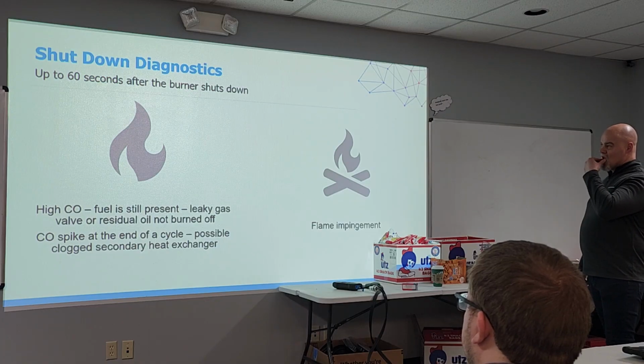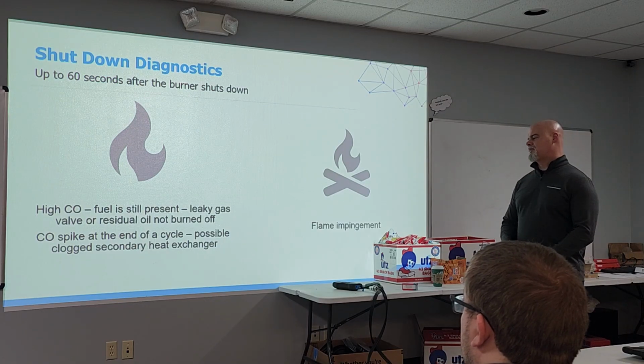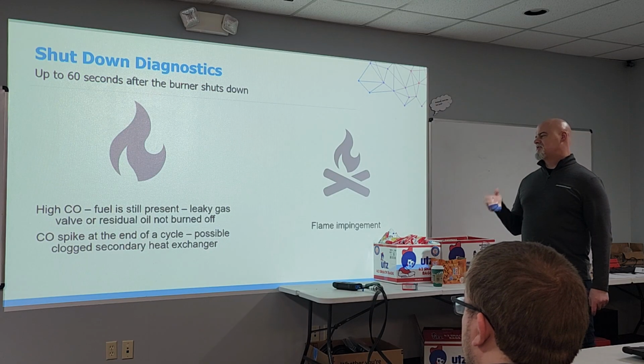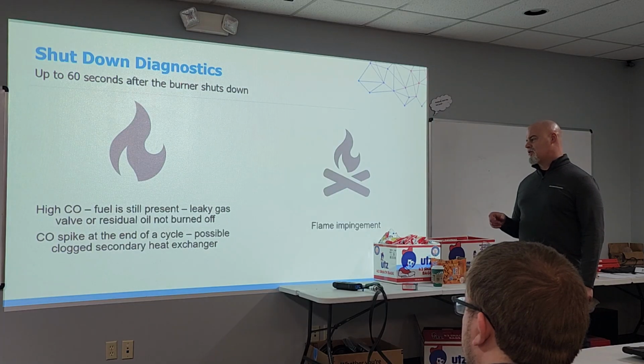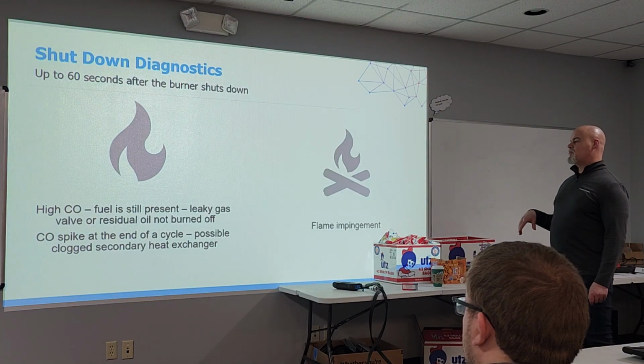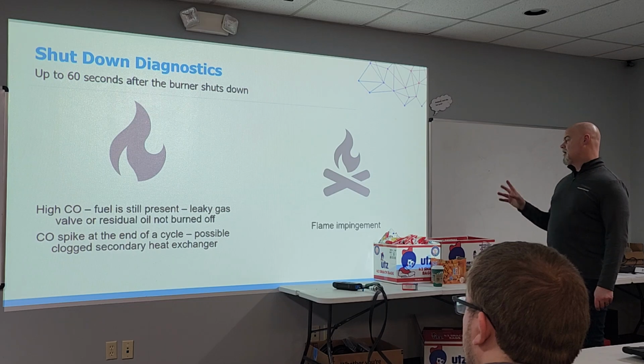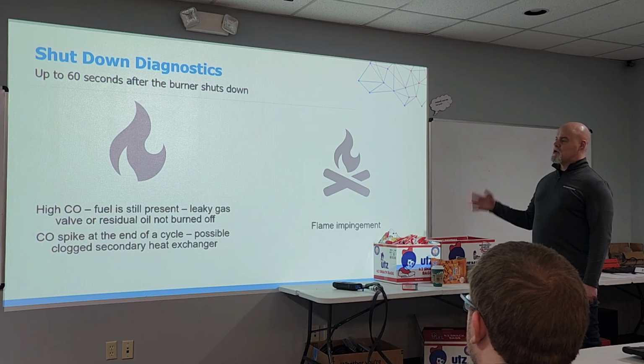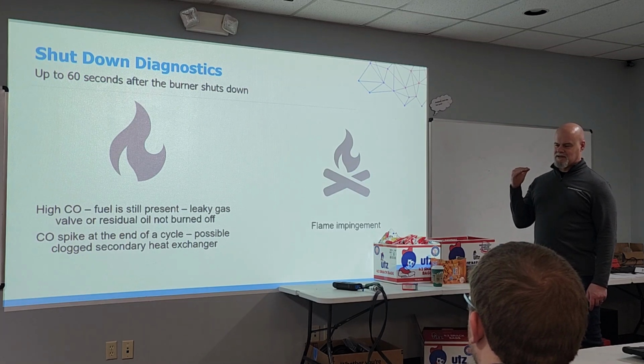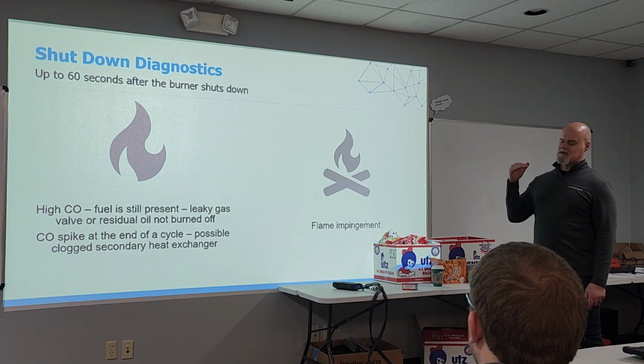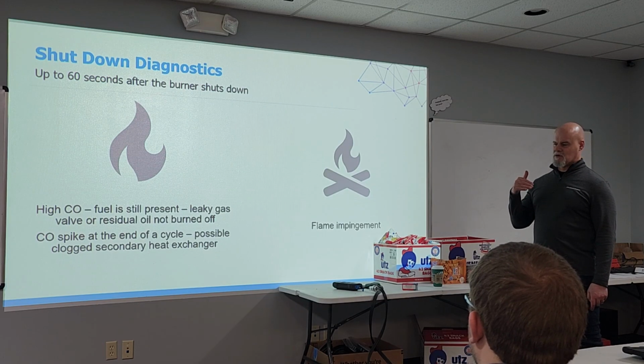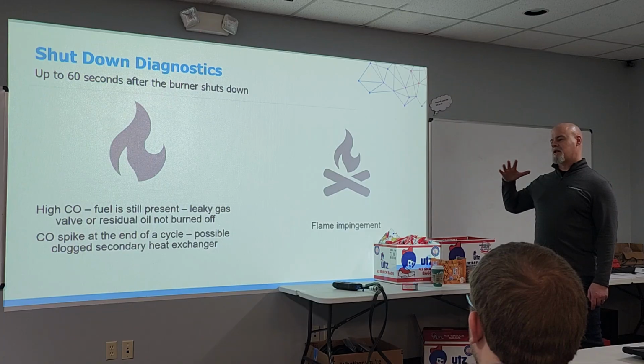And then shutdown. 60 seconds after the burner shuts down: high CO, fuel still present, leaky gas valve, residual oil not burned off, CO spike at the end of a cycle, possible clogged secondary heat exchanger, and also flame impingement. So you can see light off has its diagnostic characteristics, steady state has its own set, and shutdown has its own set. They're unique unto themselves, so if you're picking up what I'm putting down, I just gave you a roadmap to properly look at systems correctly.